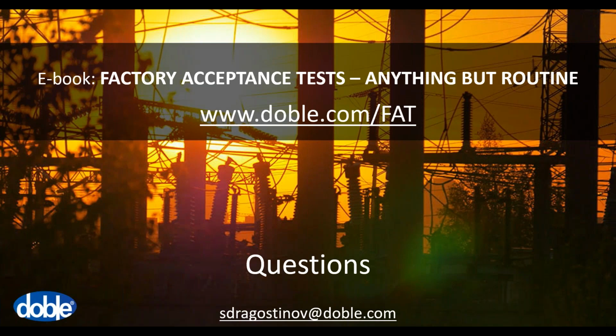So a couple of questions related to failures. Is it possible a distribution transformer less than 2 MVA can fail under the induced voltage test with a PD measurement? During the induced voltage test, every transformer can fail. I think this is the most stressful test for the insulation, and I've seen various transformers failing this test. Partial discharge measurement on these transformers is very interesting because distribution transformers are usually very small, 10 or up to a maximum of 33 kV, so partial discharge measurement is not mandatory for them. I think it's not that easy to do the measurement because you need an additional coupling capacitor. It could be done, but you need an additional coupling capacitor for each phase.